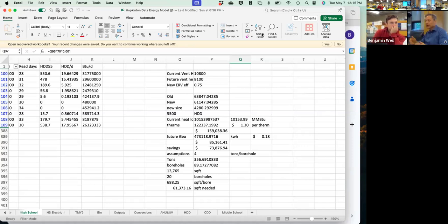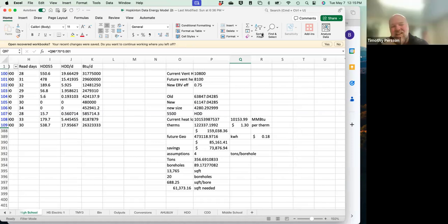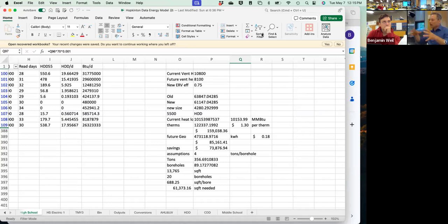Because probably if somebody hasn't really built out a full energy model and done it with care, you're using rules of thumb. When you use rules of thumb, you're basically using the experience gained by people in the 1950s when you built buildings with no insulation and energy was free. And so combine all of those things on different borehole length assumptions about the borehole capacity, which could be completely wrong, right? We just don't know until you do the test well. And we did not oversize. We got very, very precise in our sizing based on how you actually use energy.